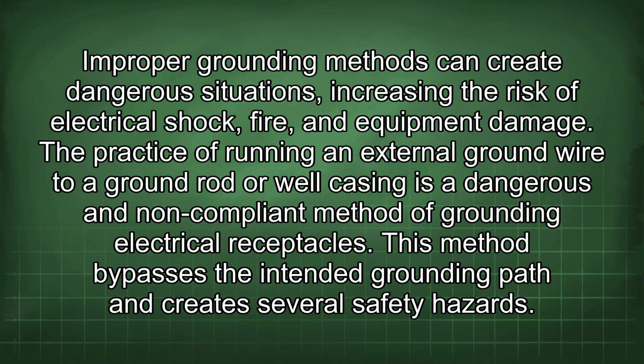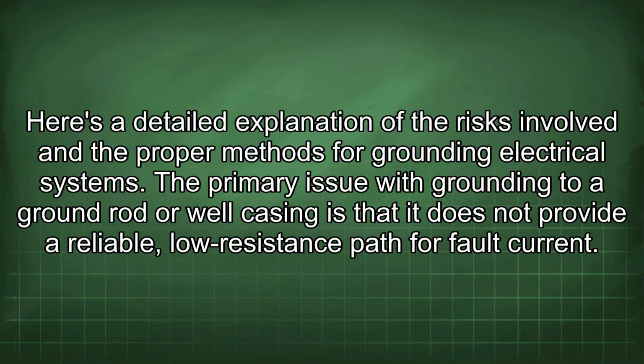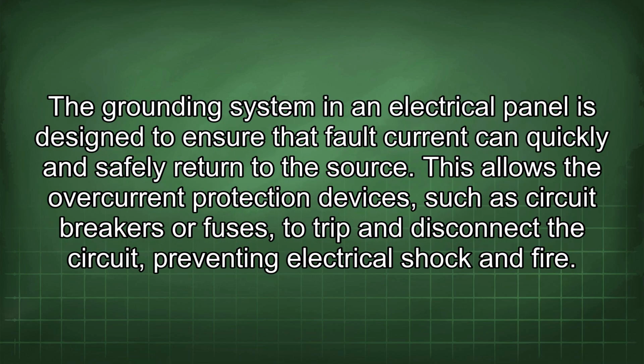The practice of running an external ground wire to a ground rod or well casing is a dangerous and non-compliant method of grounding electrical receptacles. This method bypasses the intended grounding path and creates several safety hazards. Here is a detailed explanation of the risks involved and the proper methods for grounding electrical systems. The primary issue with grounding to a ground rod or well casing is that it does not provide a reliable, low-resistance path for fault current. The grounding system in an electrical panel is designed to ensure that fault current can quickly and safely return to the source.